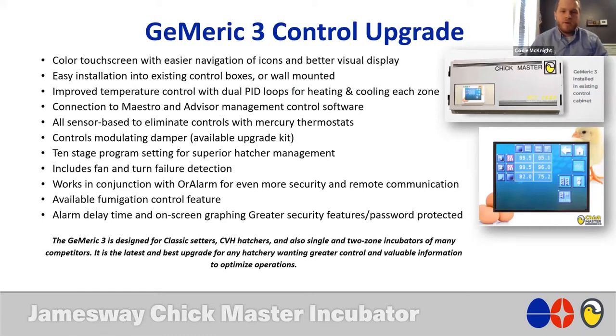When you improve your temperature control with dual PID loops, you achieve much better stability in your incubation cabinet than if you don't run dual PID loops. You get access to things like PLCs that you didn't have when you installed your older machines with the older generation of controls. Our GeMeric 3 is compatible with our Maestro and Advisor management software, and it's all sensor based, so you eliminate the need for some of those outdated mercury thermostats.